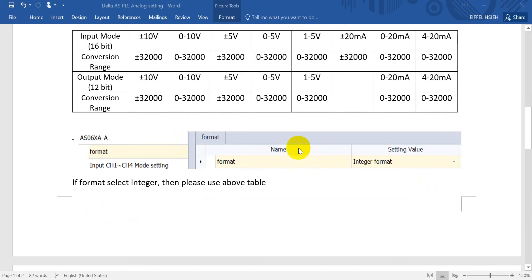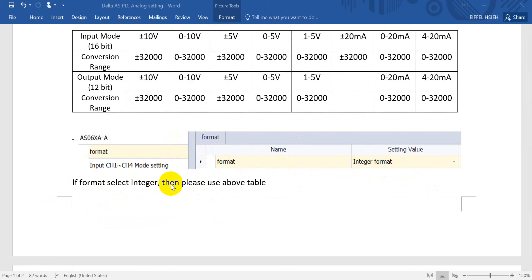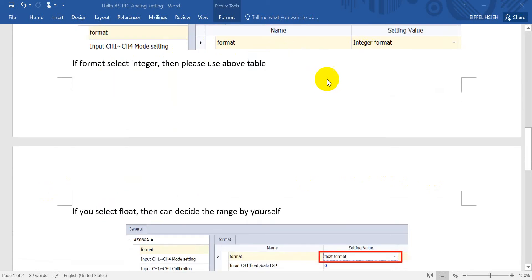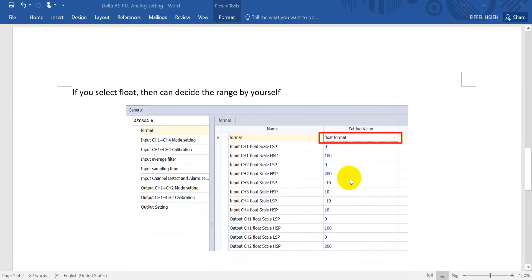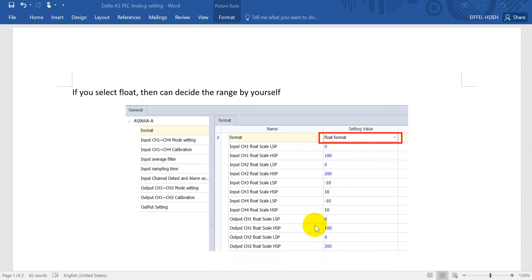I want to remind that for the format we will provide integer. If you use integer format then you have to follow the conversion range from the above table. However, if you want to use float then you can define the range by yourself. For example, channel 1 is 0 to 10 volt and we want the range from 0 to 100.